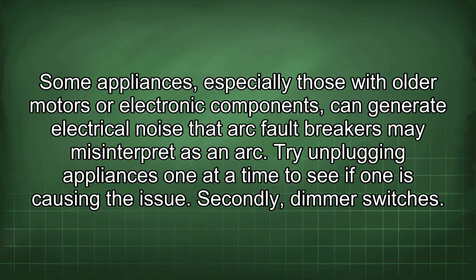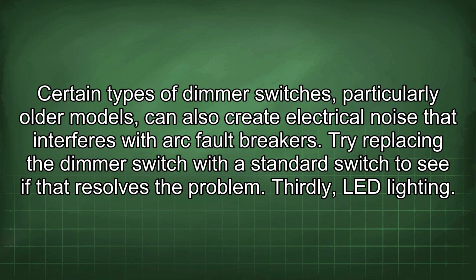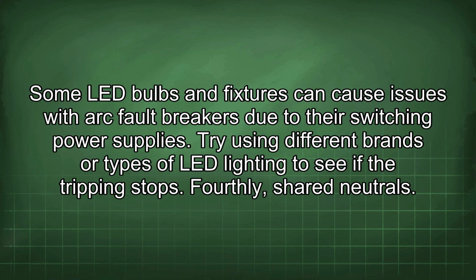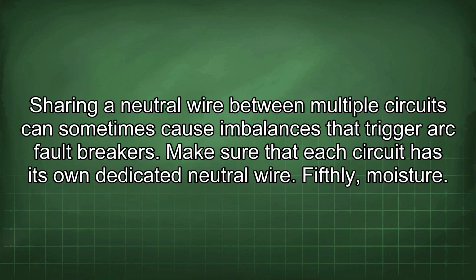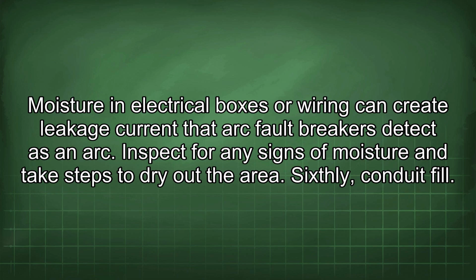Secondly, dimmer switches. Certain types of dimmer switches, particularly older models, can also create electrical noise that interferes with arc fault breakers. Try replacing the dimmer switch with a standard switch to see if that resolves the problem. Thirdly, LED lighting. Some LED bulbs and fixtures can cause issues with arc fault breakers due to their switching power supplies. Try using different brands or types of LED lighting to see if the tripping stops. Fourthly, shared neutrals. Sharing a neutral wire between multiple circuits can sometimes cause imbalances that trigger arc fault breakers. Make sure that each circuit has its own dedicated neutral wire. Fifthly, moisture. Moisture in electrical boxes or wiring can create leakage current that arc fault breakers detect as an arc.